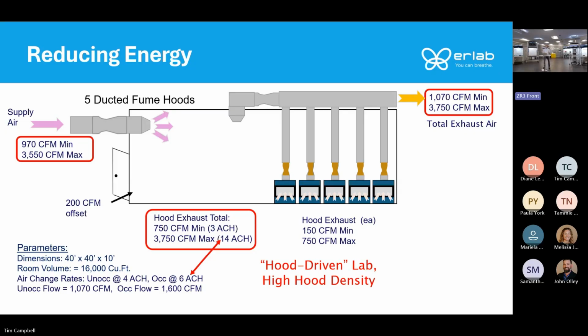So in this example, I'm just going to use a 5-hood lab that's 40 by 40, about 16,000 cubic feet of space. Your air change rate is going to be prescribed by a hazard risk analysis. And like I said, typically it's about 6 air changes per hour. So in this example, if all 5 hoods are being used at once, they're 6-foot hoods with the sash open, they're VAV hoods. So with the sash closed, they're 150 CFM.